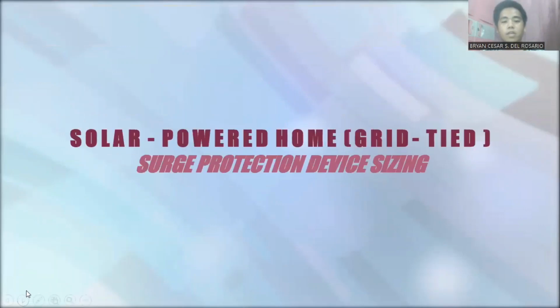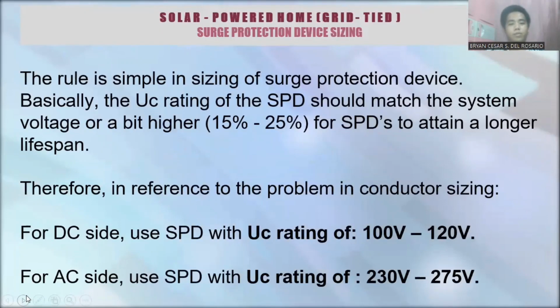So, punta tayo dito sa surge protection device sizing. The rule is simple in sizing of surge protection device. Basically, the UC rating of the SPD should match the system voltage or be a bit higher, 15% to 25%, for SPDs to attain a longer lifespan.